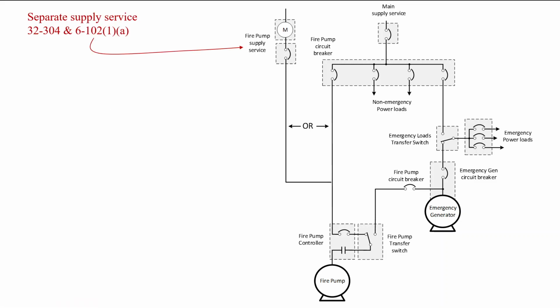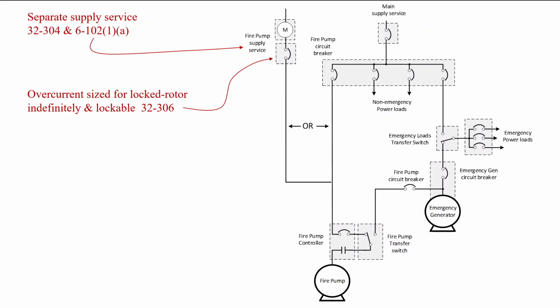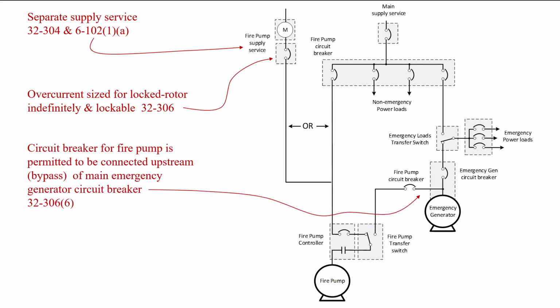The separate supply service is covered under 32304 and 61021A. The overcurrent size for locked rotor indefinitely and lockable requirement is found in 32306. The circuit breaker for the fire pump is permitted to be connected upstream or bypass the main emergency generator circuit breaker. Upstream means it's on the supply side, and the significance of having this connection of the fire pump circuit breaker on the upstream side of the main emergency gen circuit breaker is that if there were to be a short circuit in this conductor right here during an emergency event when the emergency gen was operating, this breaker alone would trip.